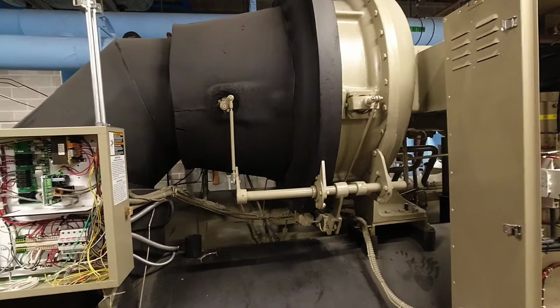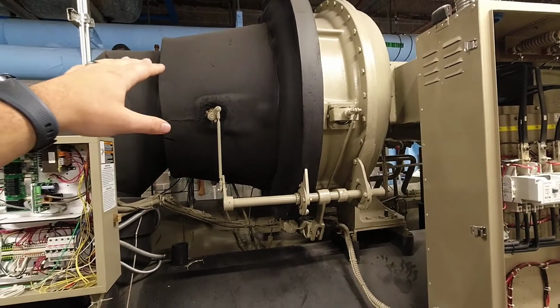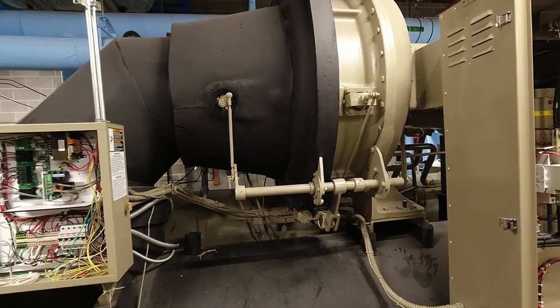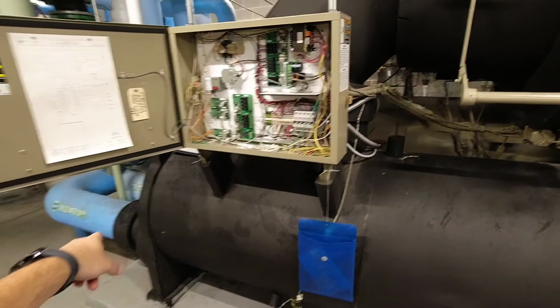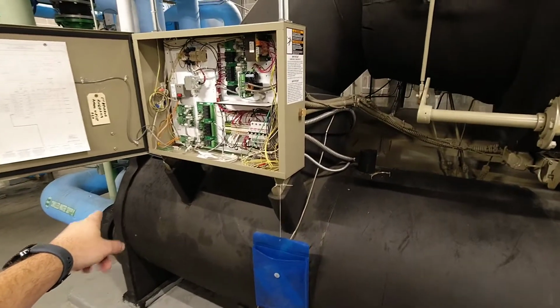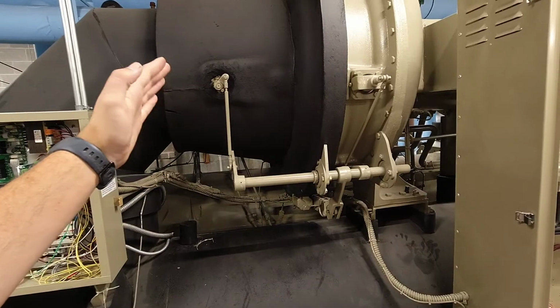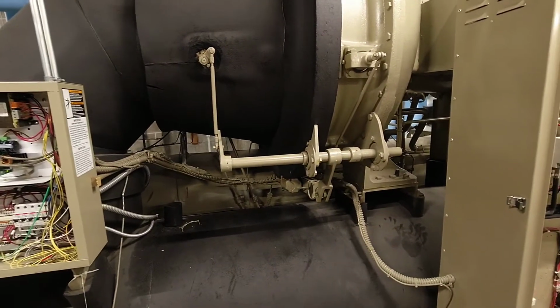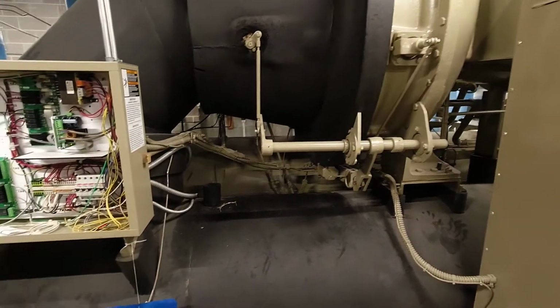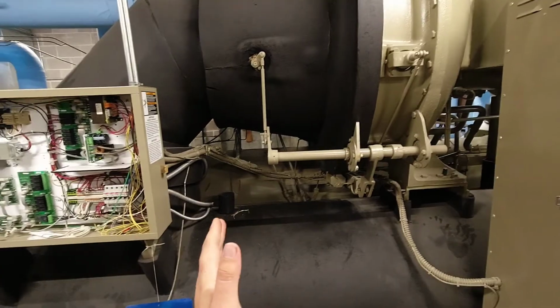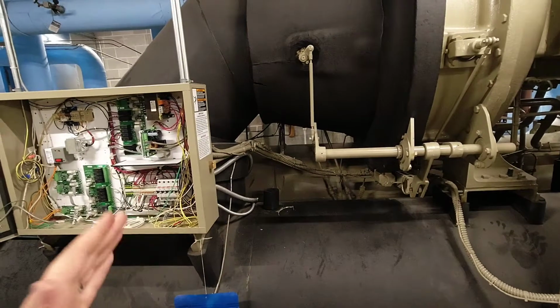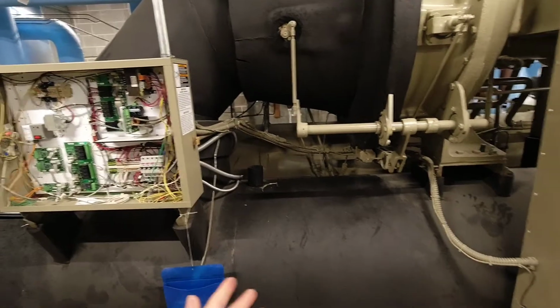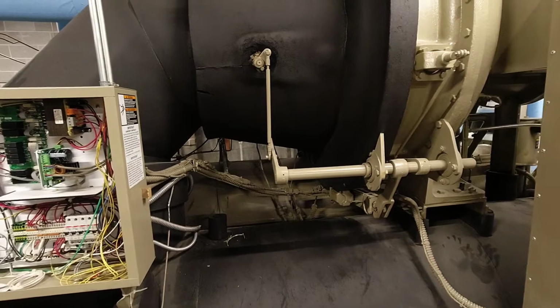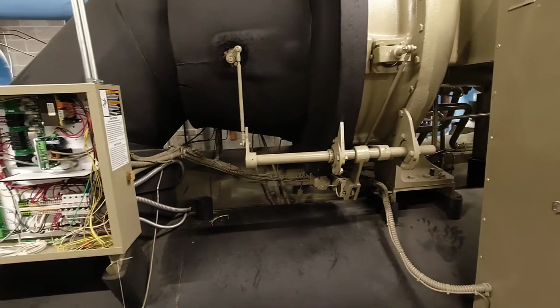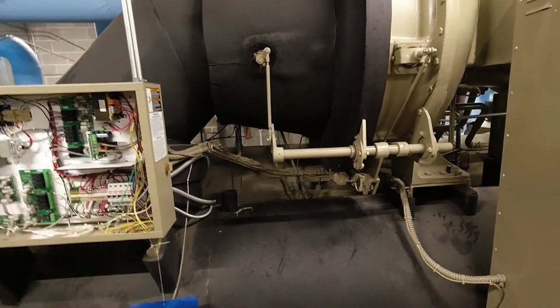The way the chiller is operating overall is once it starts up, it loads the chiller by opening the vanes. And it's paying attention to the chill water leaving. So if set point is 45, when we hit 45 degrees of leaving water, it's going to slowly start unloading the chiller and closing the vanes in order to keep the load down so that we don't overcool the loop. It will just maintain that until it can't keep the leaving water above set point, at which point it just cycles off on load, just like any other regular air conditioning system would do. When the thermostat satisfies, it turns off.